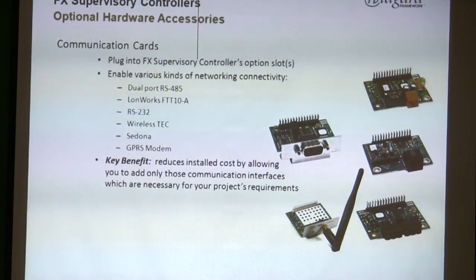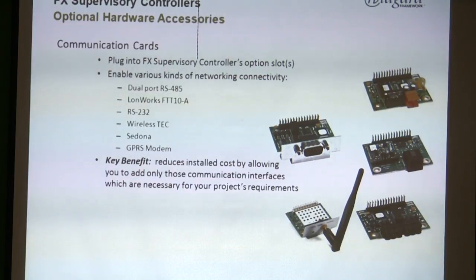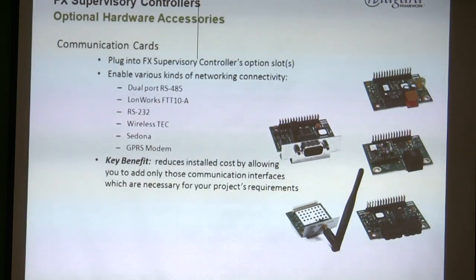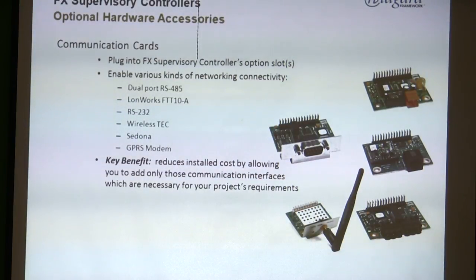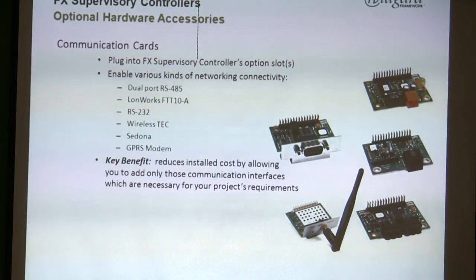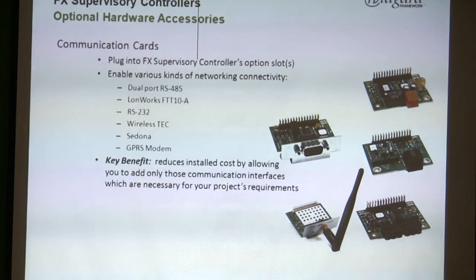With one dual-port RS-485 card you can pull in BACnet on one port and Modbus on another. There's also a built-in unbiased RS-485 that automatically comes on, but you don't want to use it unless you have to. On an FX-60 there's a spot for two more dual-port RS-485 cards, giving you four plus one — five total. If you add LonWorks, you lose those two and just get one back since there's only one slot for LonWorks.